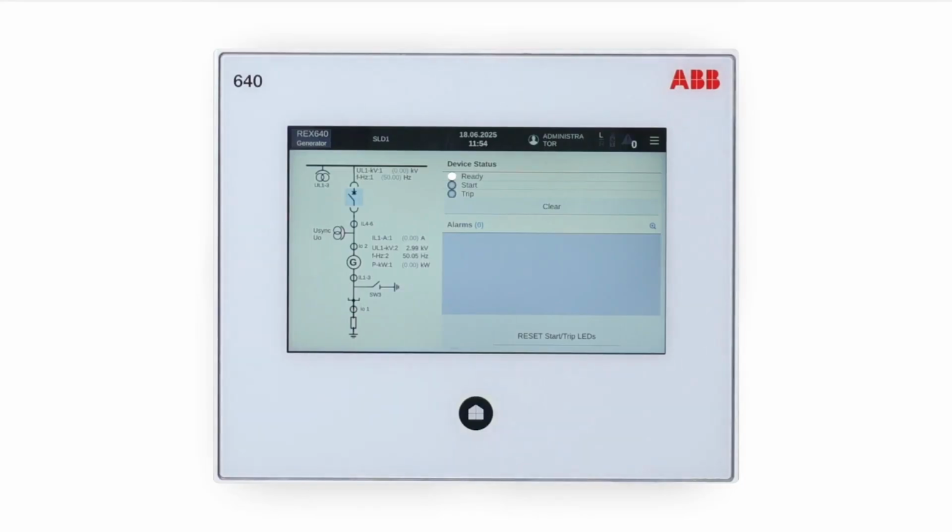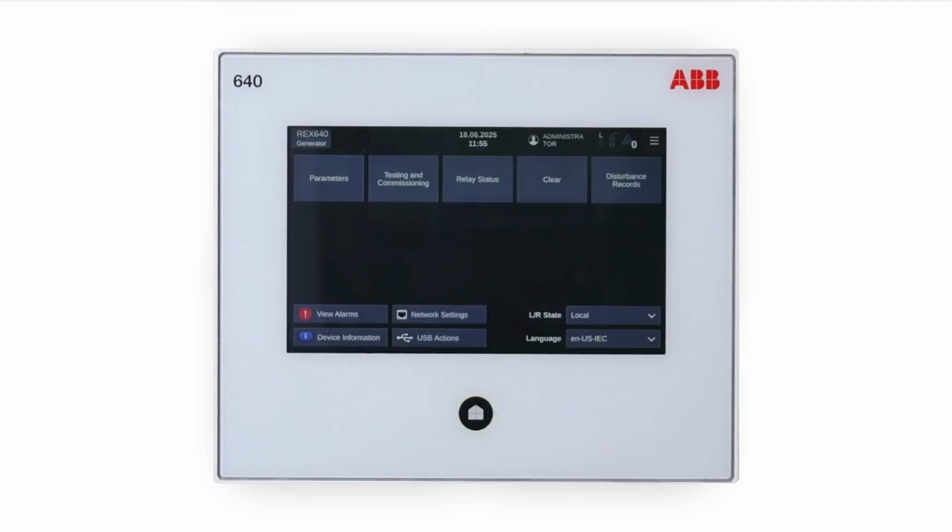Enabling Web HMI. Connection to Web HMI can be established using different communication card ports or the LHMI service port. WHMI is disabled by default and can be enabled with a setting parameter. As only secure communication is supported for the WHMI, it must be accessed from a web browser using the HTTPS protocol. To enable the WHMI, select Parameters.